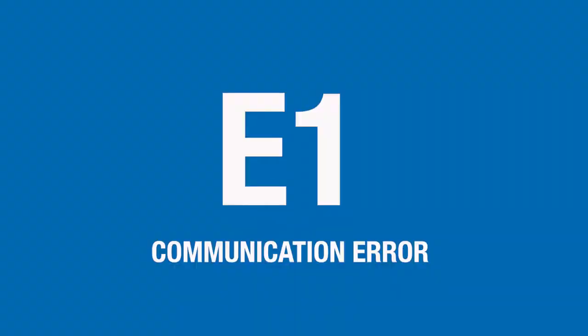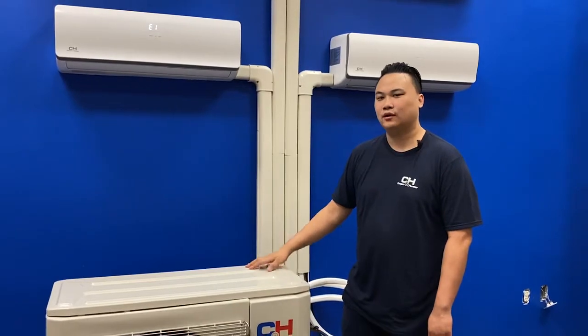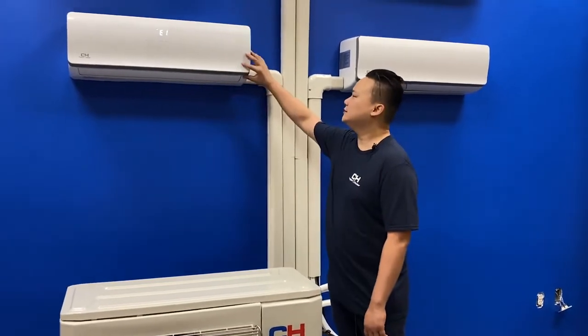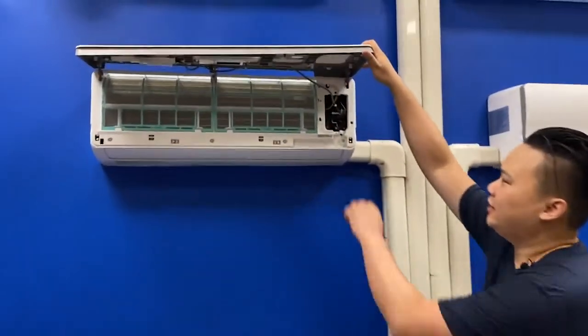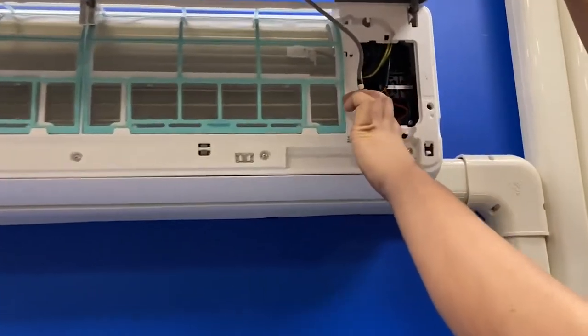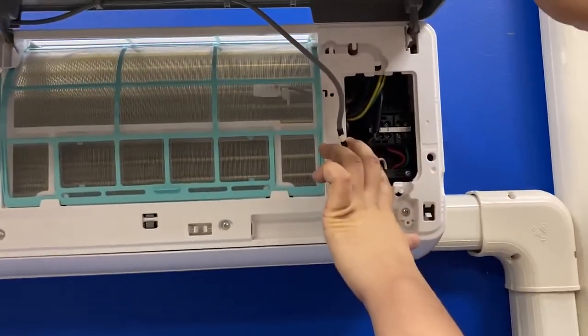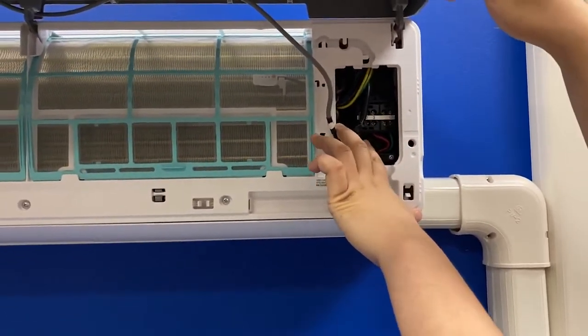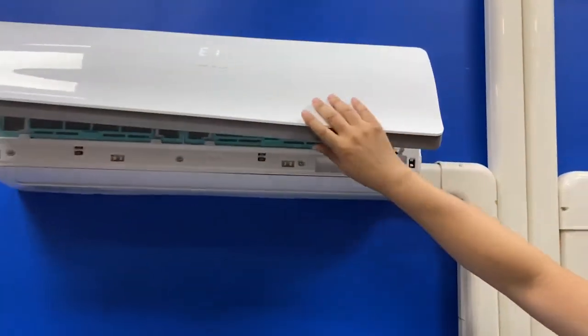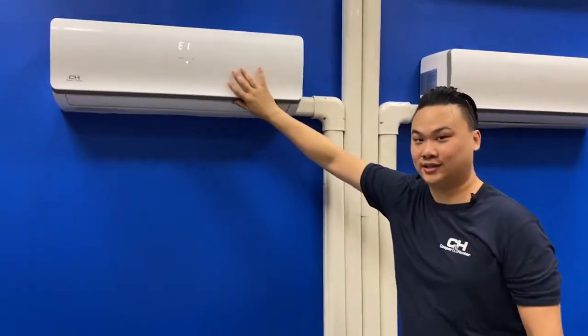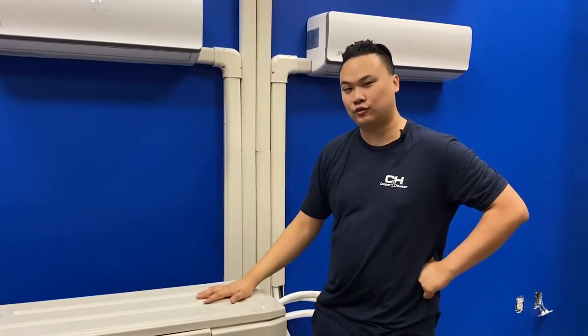If your indoor unit is displaying an E1 error code, that indicates communication error. What I would check first is to make sure that at the terminal, your connections match your outdoor terminal. In this case, it's white, black, red.